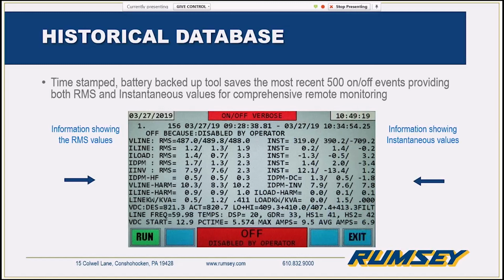I don't have it all on here, but for example, with this we have time-stamped 500 on-off events and 1,000 reset events. We have what we call flight data recorder information that we use to make different waveforms to be able to evaluate internal and external information to the filter. And again, with this example here, looking at the instantaneous and the RMS values to really get a full picture of what's going on.